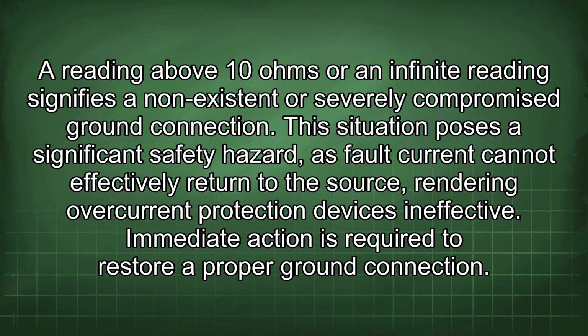A reading above 10 ohms or an infinite reading signifies a non-existent or severely compromised ground connection. This situation poses a significant safety hazard, as fault current cannot effectively return to the source, rendering overcurrent protection devices ineffective. Immediate action is required to restore a proper ground connection.